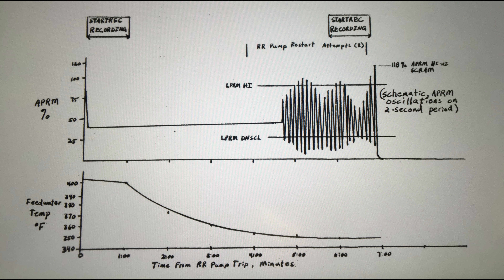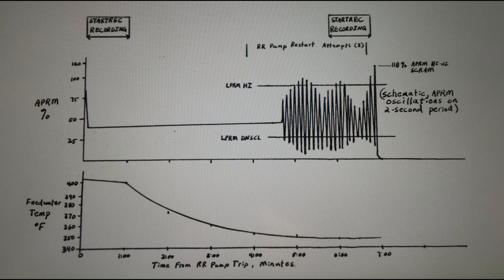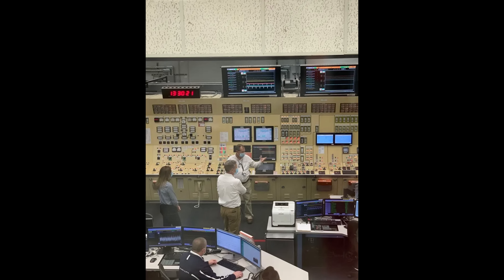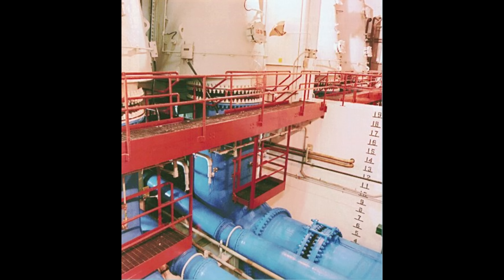Surprisingly, there was no core damage during the entire event. The operators had had their lucky escape. The investigation concluded that, aside from the initial actions leading to the recirculation pumps tripping, operator error did not play a factor in this accident. Instead, the issue was with the operating instructions they had been trained by. The technical specifications in place at LaSalle at the time were vague. And while a 1984 brief by General Electric — the company that designed the boiling water reactor involved in the accident — had specified that control rods should have been inserted when the recirculation pumps tripped to get themselves out of the region of instability, this had never actually been incorporated into any operating guidelines at the time.